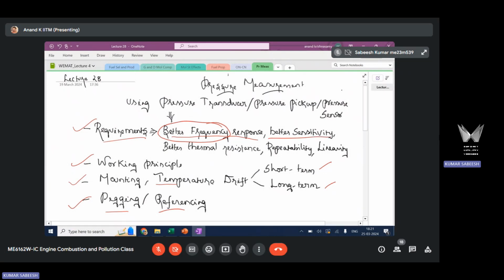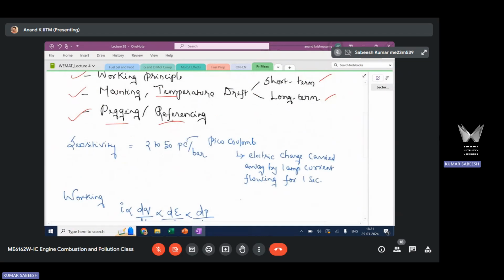Also, the sensor should have a better sensitivity. What is sensitivity? It should capture even small pressure changes. Sensitivity is output by input in simple terms. The output from the sensor is basically in terms of PC. PC is picocoulomb. What is coulomb? Electric charge. Okay, so coulomb is the electric charge carried by a 1 amp current for 1 second. This is the definition of coulomb, and here we are talking about picocoulomb. Pico is 10 power minus 12. So you can imagine, such a very small charge is being generated by the sensor with respect to the pressure changes. So sensitivity is output by input. It generates an output of 2 to 50 picocoulomb. That is the electric charge for a particular pressure value. So 2 to 50 picocoulomb per bar is a typical sensitivity of the sensor.